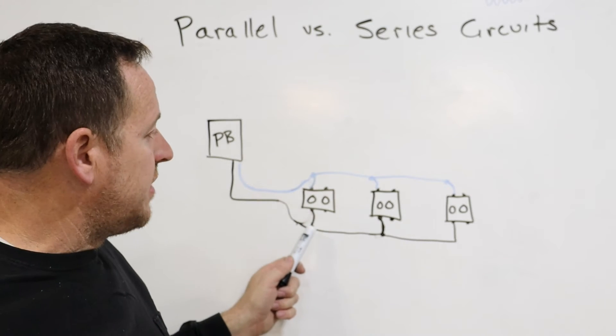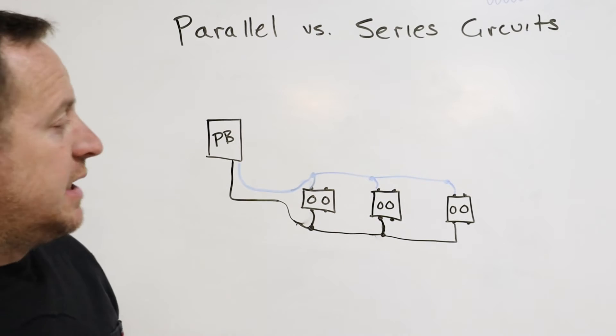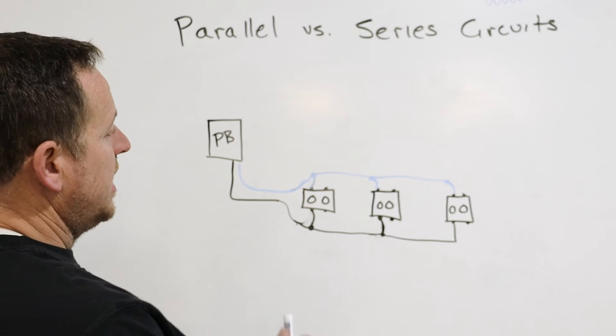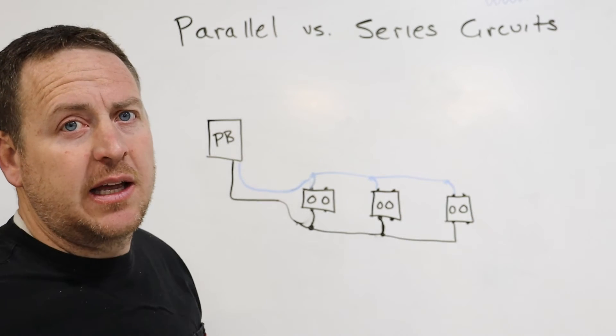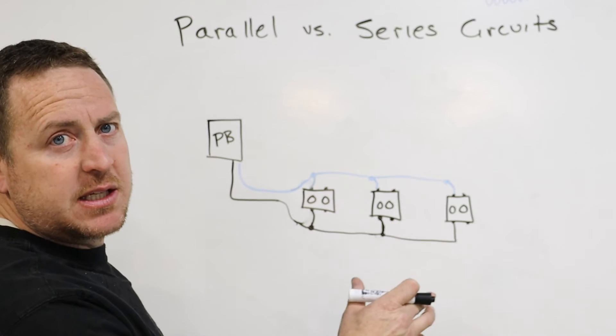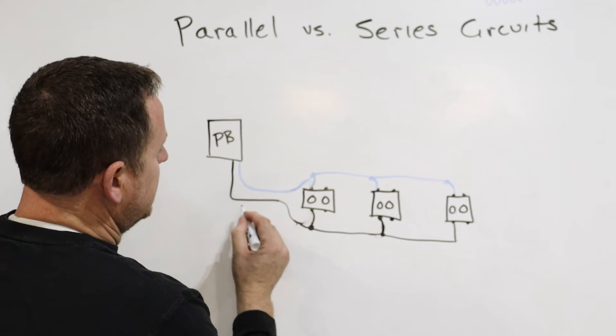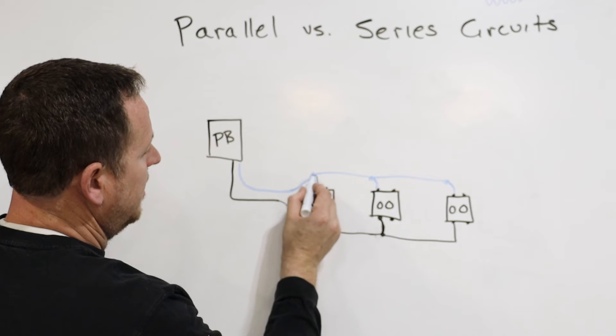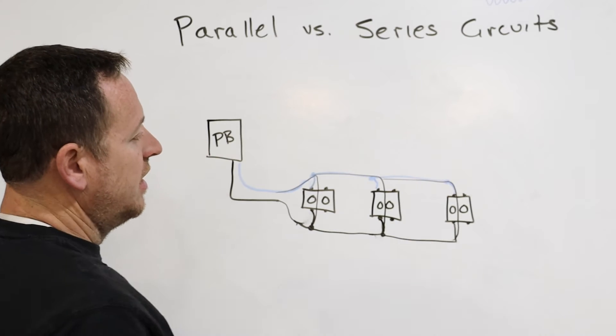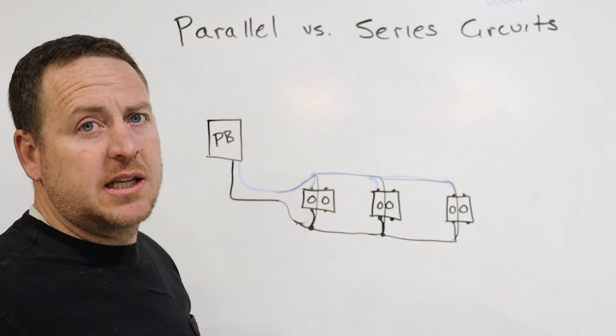Your hot wire comes over, gets wired under the pigtail, powers the first outlet, then continues on to power the second outlet, and continues on to power the third outlet. If one outlet stops working, it's not going to take out every other outlet — it's not like the old Christmas bulbs where one device goes out and they all go out. What that means is we have a completed circuit here, a completed circuit here, and a completed circuit here.